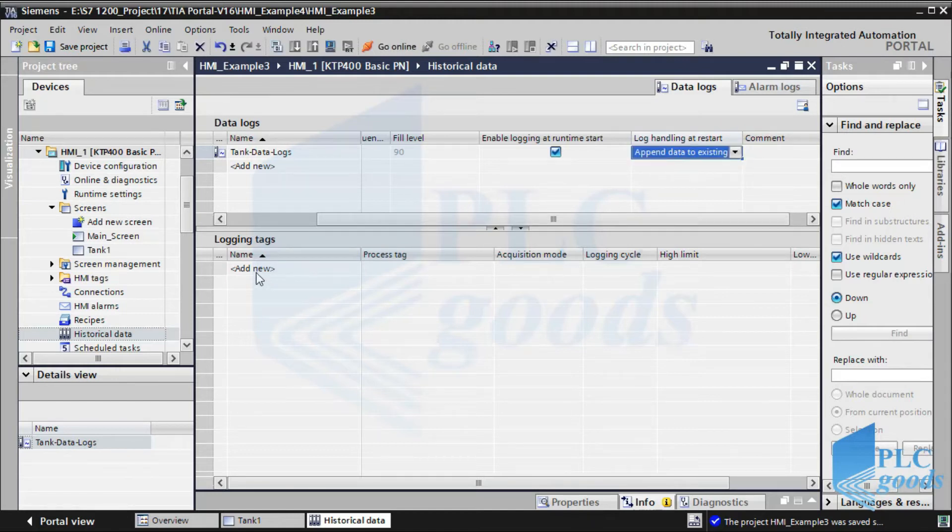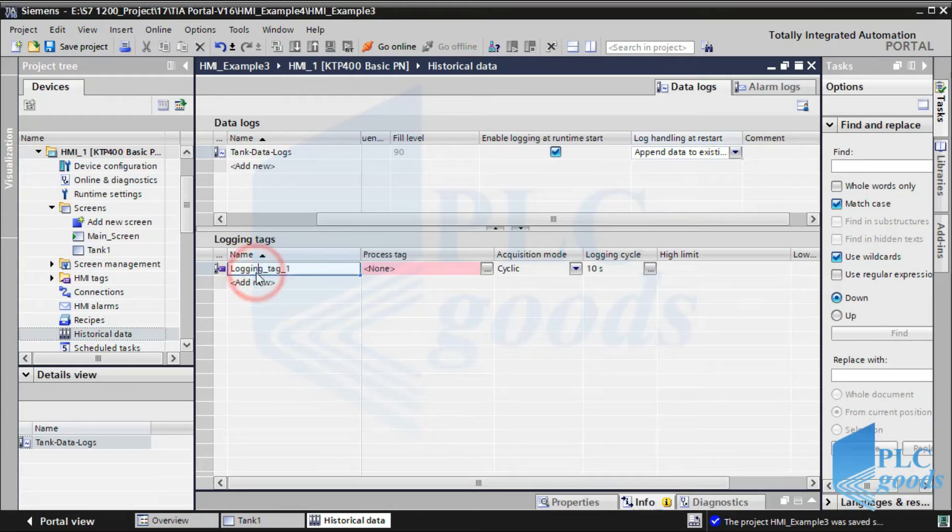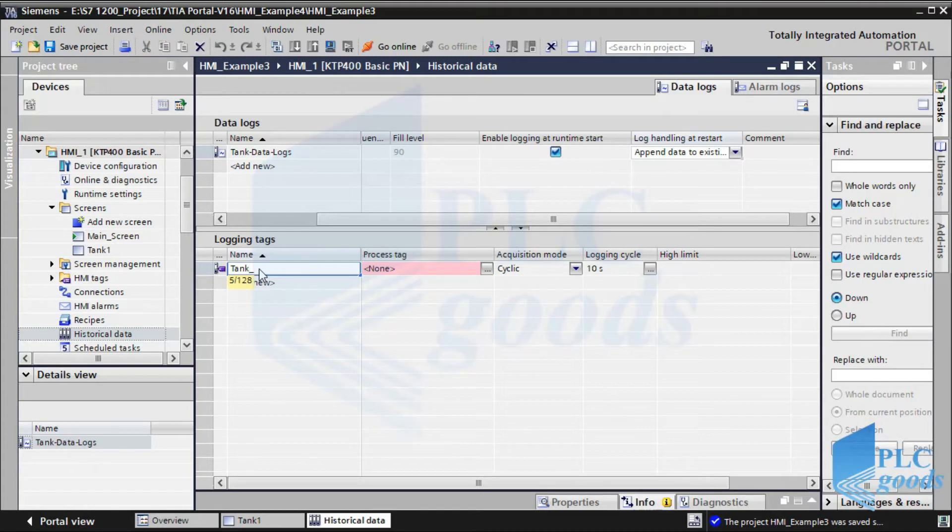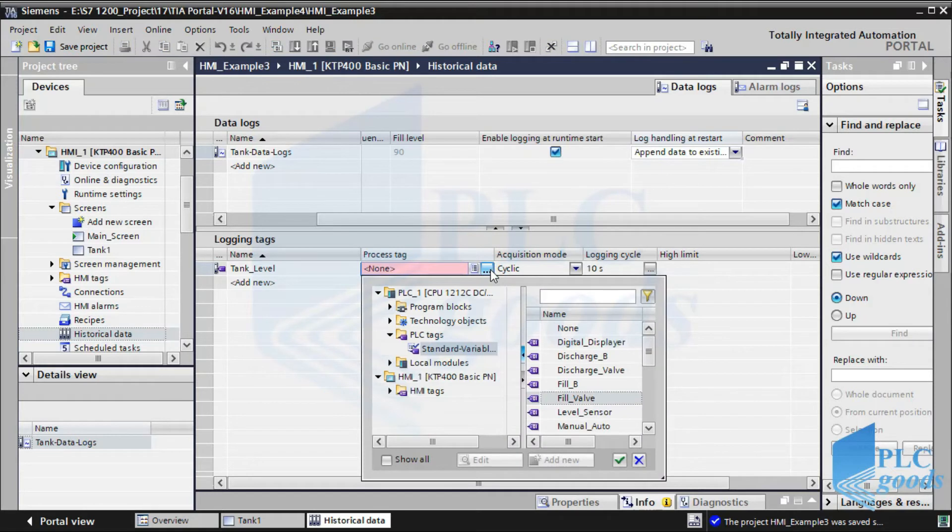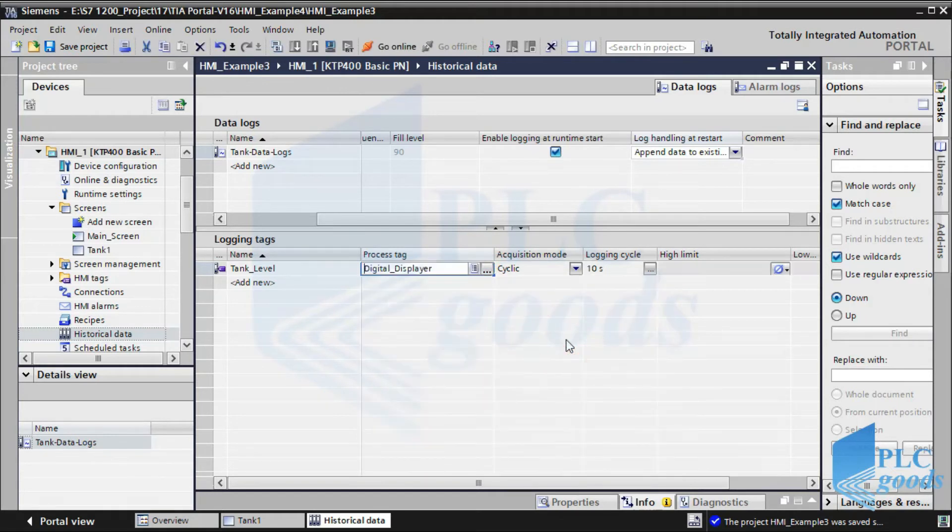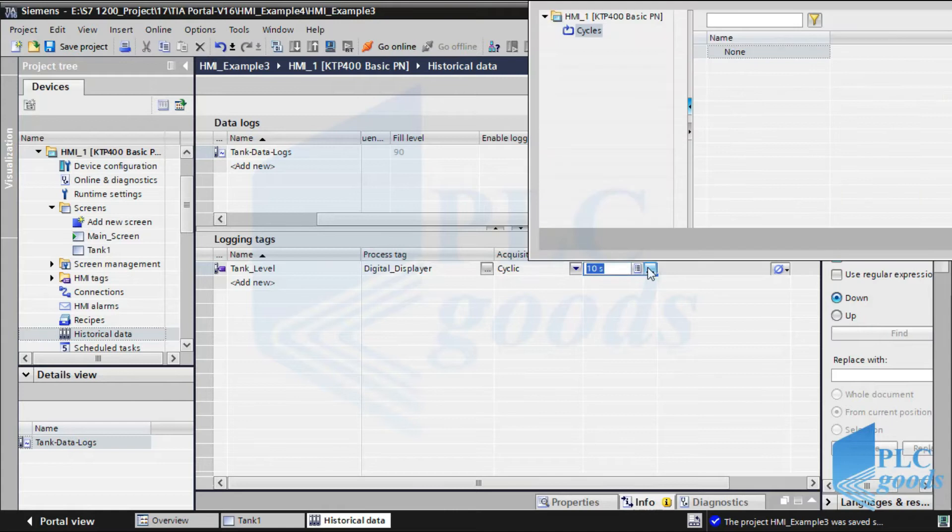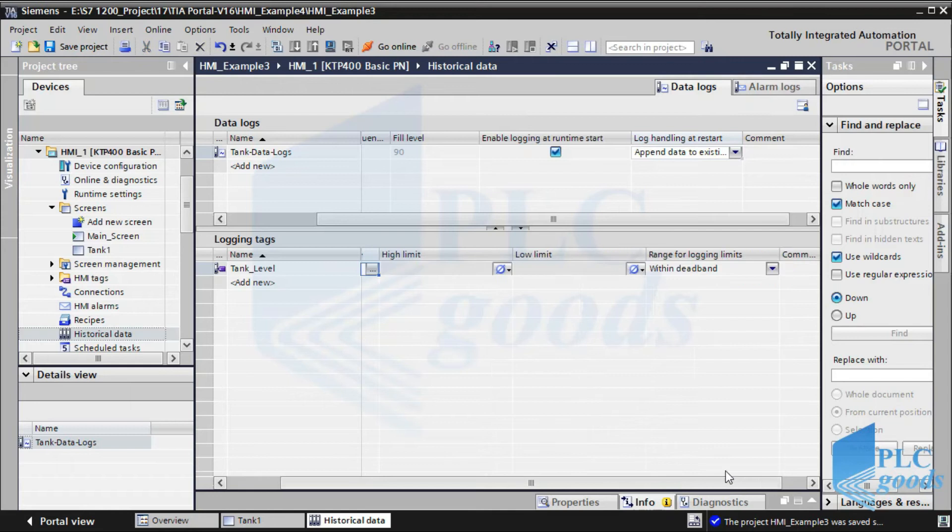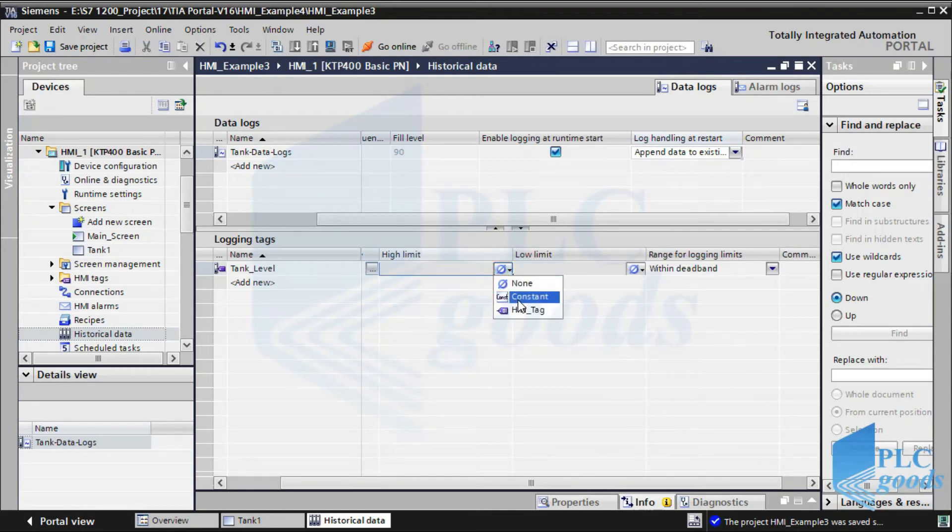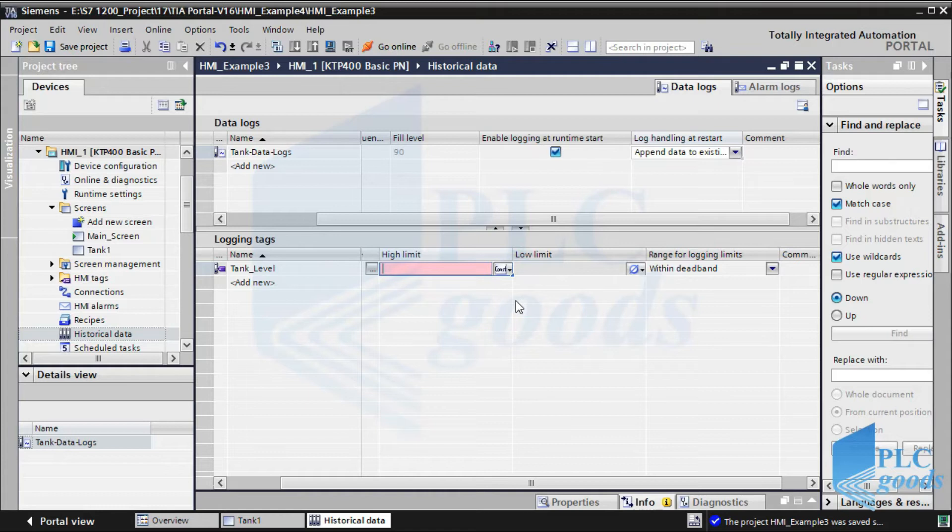Here, we must determine data whose value should be logged. First, I want to record tank level liquid. Then, its PLC tag must be entered. We can determine the logging cycle time. Also, define its lower and upper bounds and select its logging's limit range.